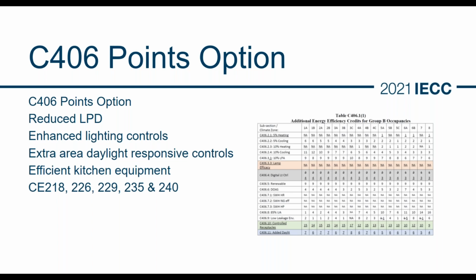So this is the new format that's being proposed right now in the IECC. Again, it does level the playing field significantly because now everything is on the same level of efficiency. As part of this process, we also took a look at some of the problems and issues that we're having with the current format of the code, and there have been some issues with equipment efficiency, because right now you're required to have a 10% increase in efficiency for both your heating side and your cooling side if you have, for example, a gas electric system on your roof, a package system on your roof.